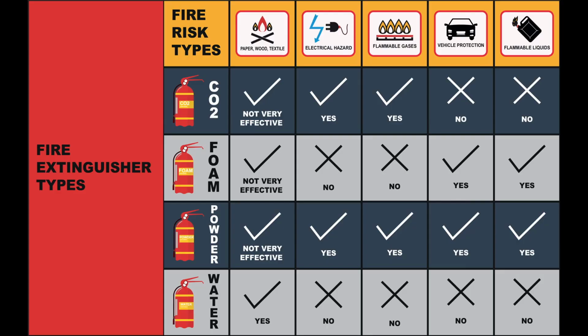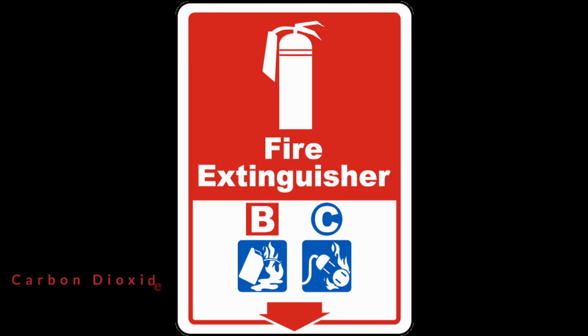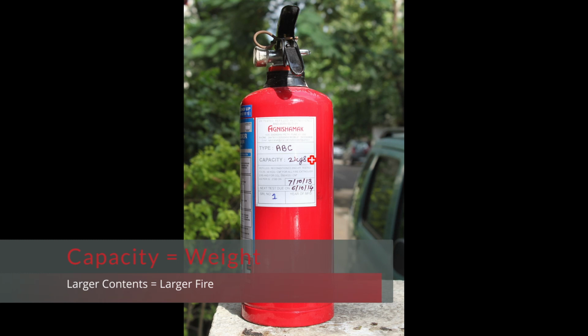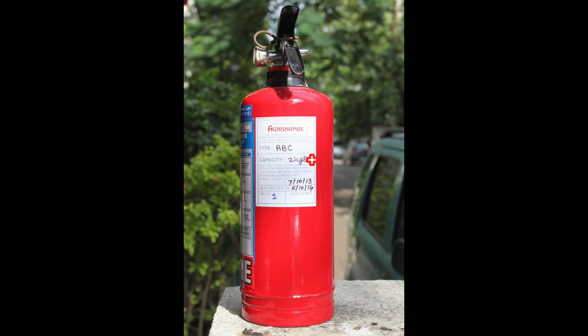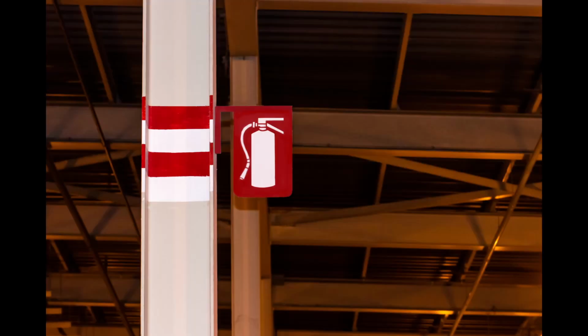Fire extinguishers can address multiple fire types and will display relevant class labels, such as ABC or BC. ABC extinguishers typically have a dry powder agent, while BC ones often use carbon dioxide, effective for electrical and liquid fires. Some extinguishers feature a number before the class letters, indicating the fire size they can combat. A higher number means it can handle larger fires. Tip: get acquainted with extinguisher labels in your vicinity well in advance of any potential need to use them.